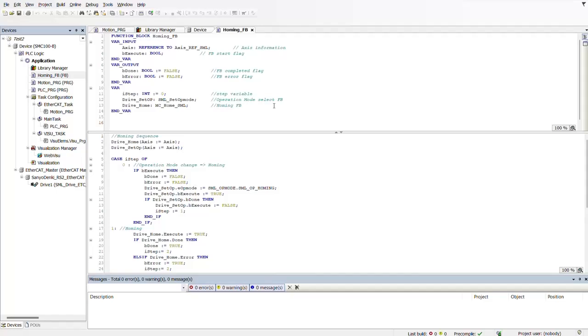Right here in this new function block we have our inputs, outputs, as well as our local variables. In our inputs we basically reference our axis object — these input parameters provide information about the axis to be homed. Then we have our execute — this is basically a boolean flag that serves as a trigger to start the homing procedure when it's set to true. Then we have our outputs: two boolean commands — the first one indicates whether the homing procedure has been completed, and then we have the error command.